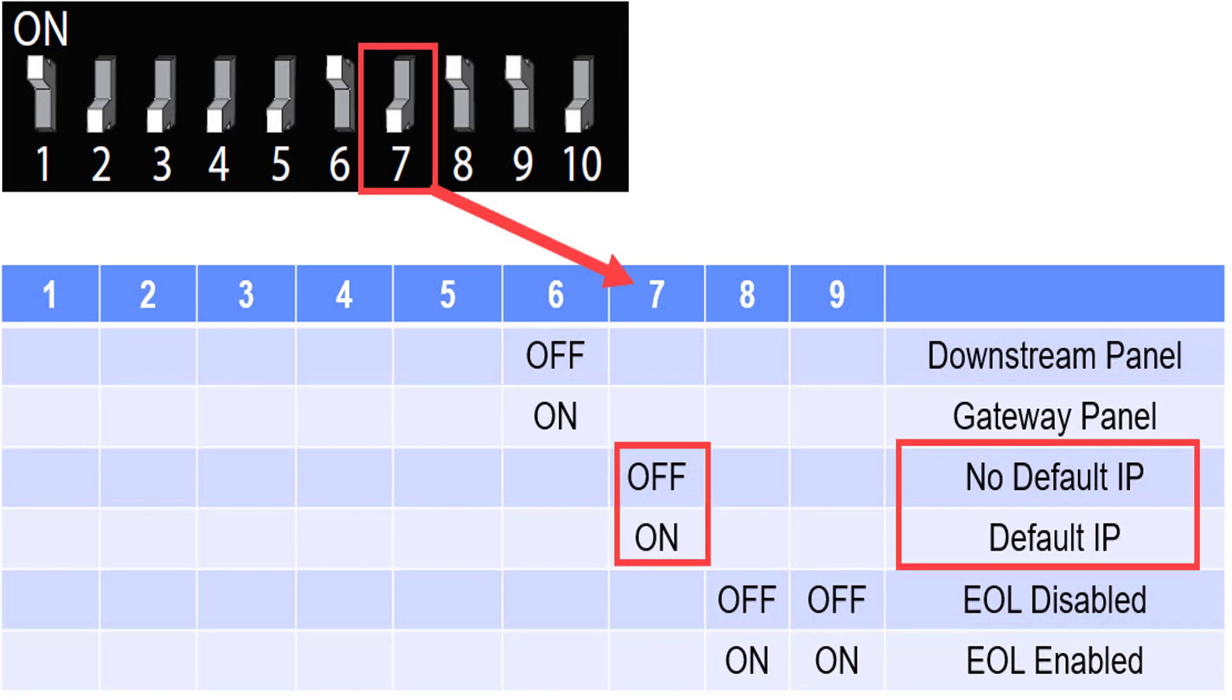DIP switch 7 deletes the current network settings of the panel and forces it back to the default IP address of 192.168.1.150 with subnet mask 255.255.255.0. If turned on, you must log in to the web interface to change the IP address according to the network requirements.